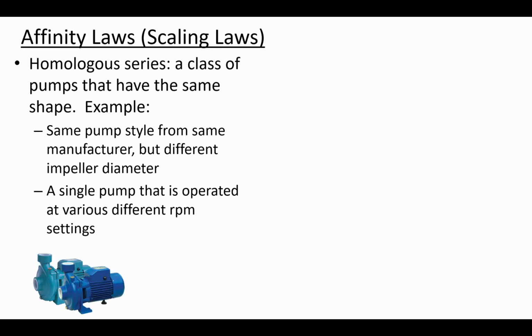Affinity laws, sometimes called scaling laws, are a way to figure out what happens when you change some parameter associated with a pump. Pumps often come in families or have parts that are replaceable and interchangeable. For example, a pump designed by a manufacturer may have different sized impellers that can be put into the pump.